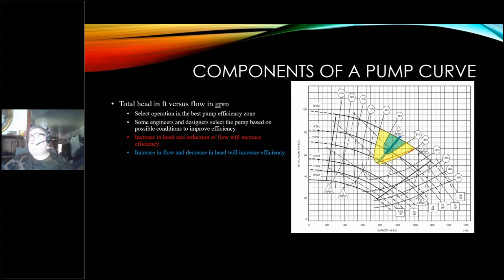If you go with the next set, you get a wider, what you could call a sweet spot, but you're losing 1% in efficiency, but it gives you a wider operating range. Okay. So if we pick at the very bottom of this, we can go all the way down to, what is that, 790 or 780 GPM. And at the very high end, we can go up to 1200, okay, and stay in this relative zone of good efficiency, around 80%. But then I have to look at the resistance also. So the highest resistance I can have in this system is 83, somewhere in there, and the lowest resistance to get the best operation is 57 or so. No, that's 53.